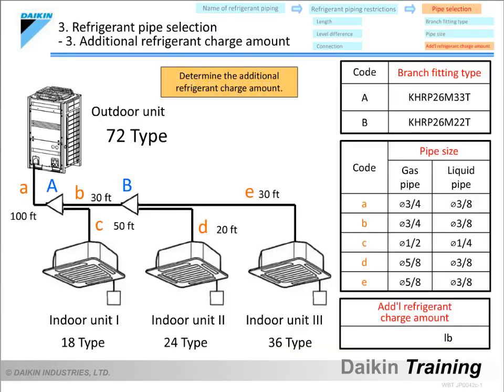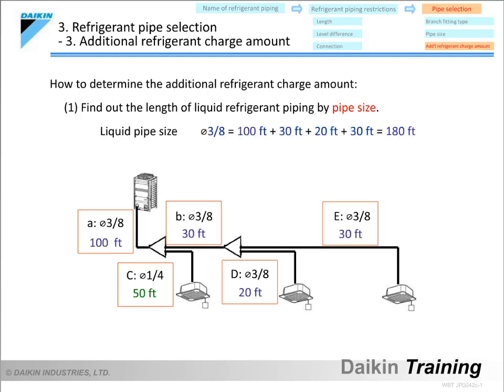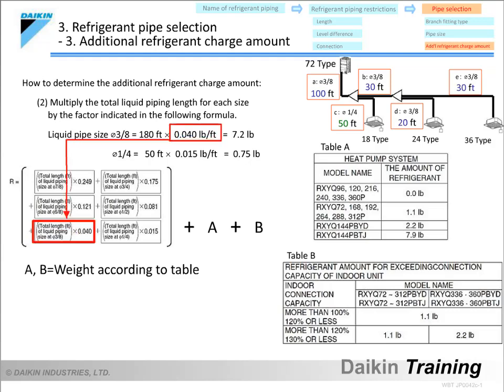Next, let's look at how to determine the amount of additional refrigerant charge. We use the true pipe sizes and actual piping lengths of the liquid refrigerant piping, as opposed to equivalent lengths. First, find the liquid piping length for each pipe size. In this case, the total length of ⅜ inch pipe is 180 feet and that of ¼ inch pipe is 50 feet. We then multiply the lengths by the indicated multiplier: 0.040 pounds per foot for ⅜ inch pipe and 0.015 pounds per foot for ¼ inch pipe, resulting in 7.2 pounds for the ⅜ inch pipe and 0.75 pounds for the ¼ inch pipe.